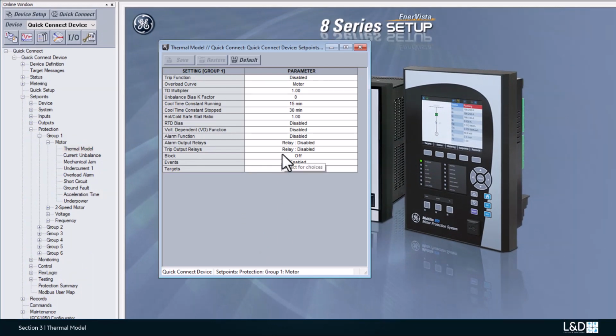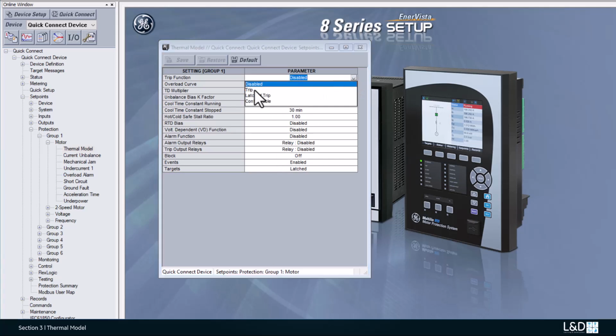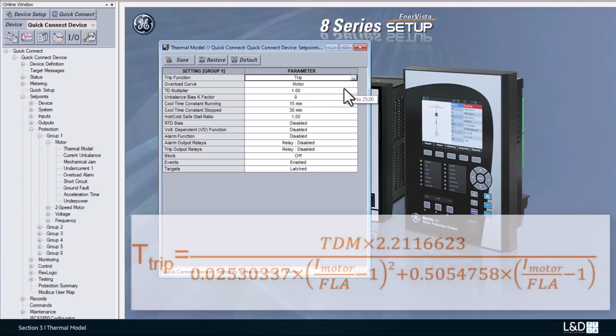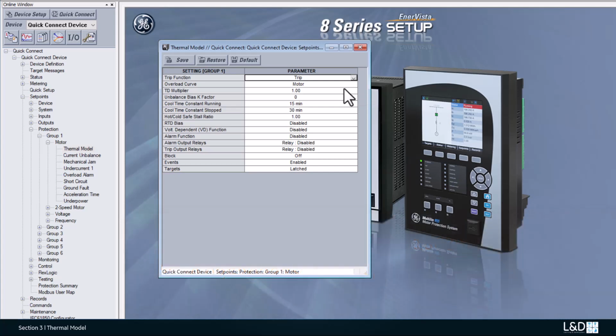So for these examples, we're going to set these parameters to the thermal model first. The trip function is set to trip, and also the time dial will keep the default 1, and also using the overload curve type to be motor. When the motor curve is selected, the trip time is calculated with this equation.